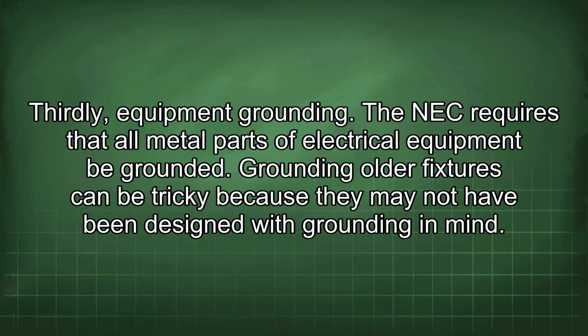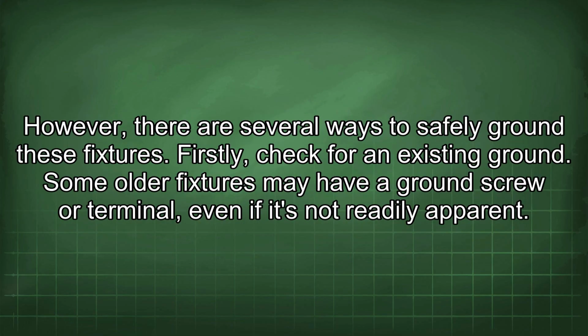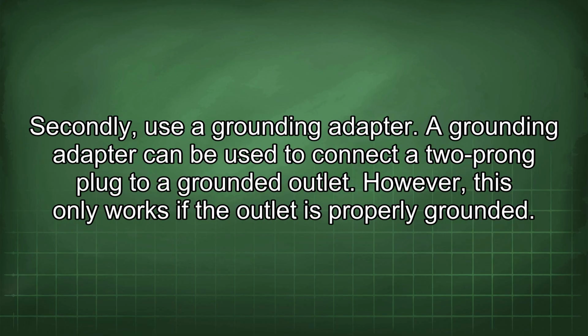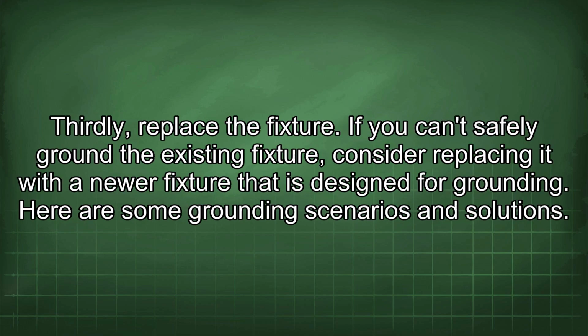Grounding older fixtures can be tricky because they may not have been designed with grounding in mind. However, there are several ways to safely ground these fixtures. Firstly, check for an existing ground. Some older fixtures may have a ground screw or terminal, even if it's not readily apparent. Secondly, use a grounding adapter. A grounding adapter can be used to connect a two-prong plug to a grounded outlet. However, this only works if the outlet is properly grounded. Thirdly, replace the fixture. If you can't safely ground the existing fixture, consider replacing it with a newer fixture that is designed for grounding.